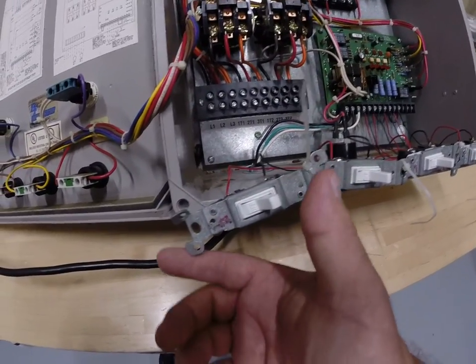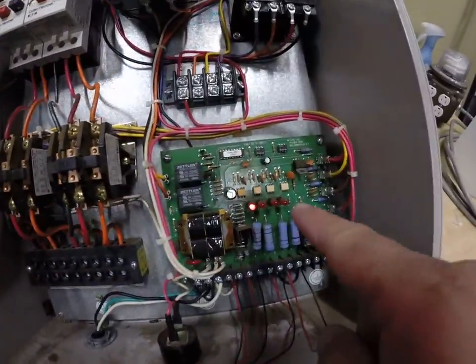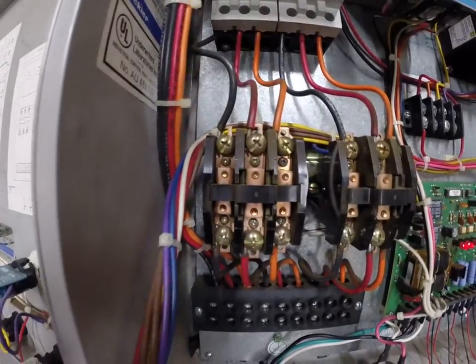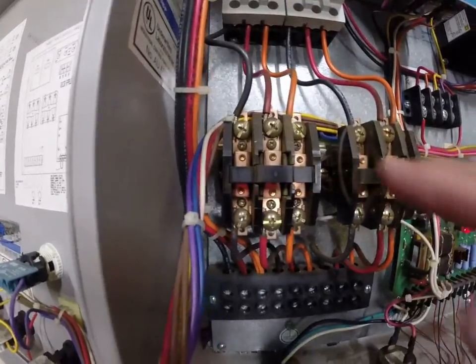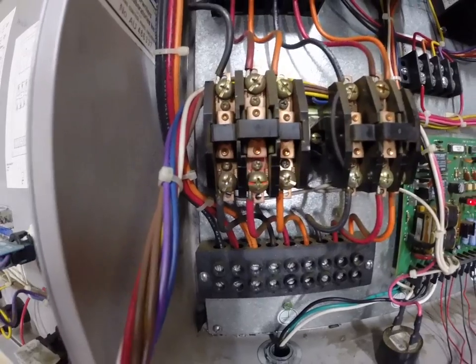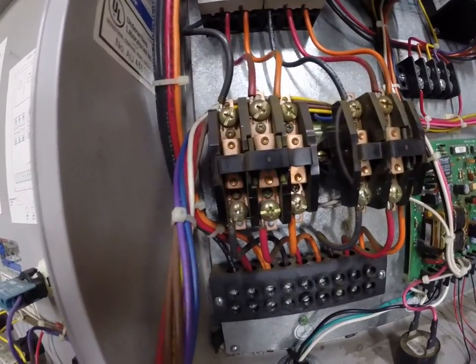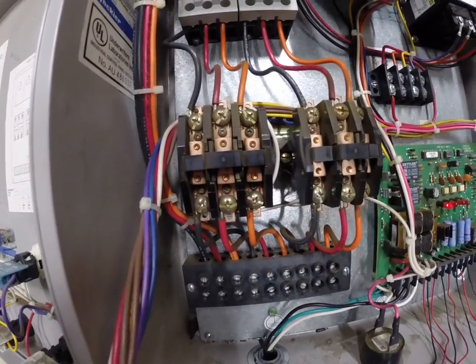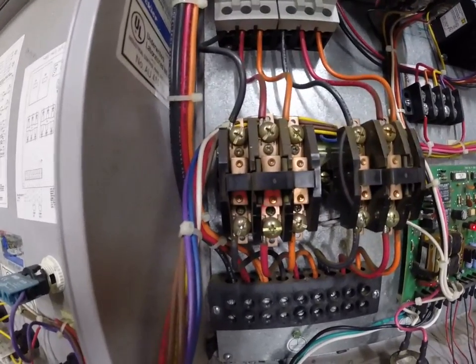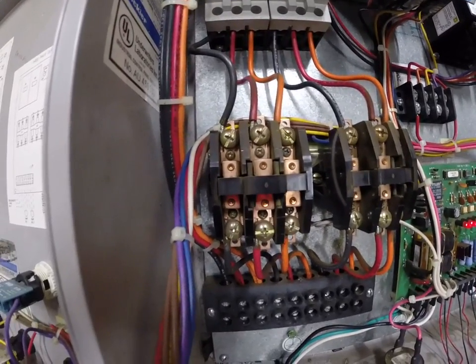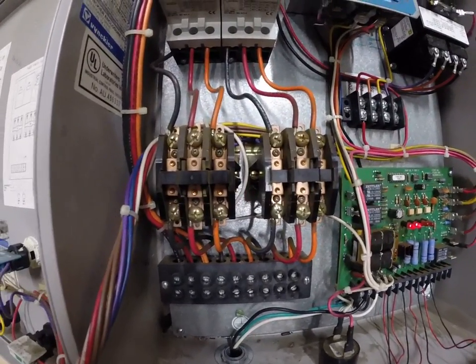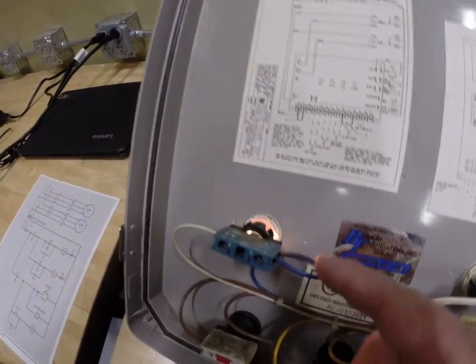You'll see what happens. This is my float switch number one. You can see the circuit board turned on. Float switch number two. You heard that contactor pull in, and that's this contactor. I'm going to do it again so you can see it. Float switch number one—pretty much nothing, it's just letting you know that there is water in the tank. Float switch number two gets activated, and now all of a sudden I've got my contactor pulling in. I have some indication. I'll show you what that is after. I have an indicator light letting me know my pump motor is running.